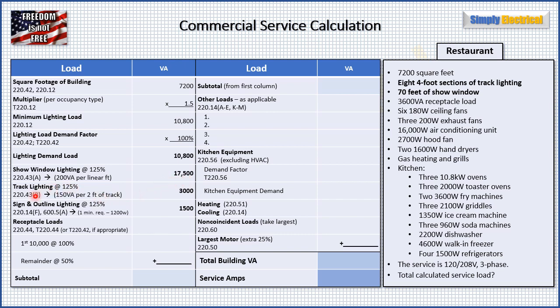Next, track lighting: per 220.43B, we need 150 VA per two feet of track. We have eight four-foot sections, so 8 times 4 gives us 32 total feet. Dividing by 2 gives us 16, and 16 times 150 VA is 2,400 VA. Adding the extra 25% for continuous load takes us to 3,000 VA.